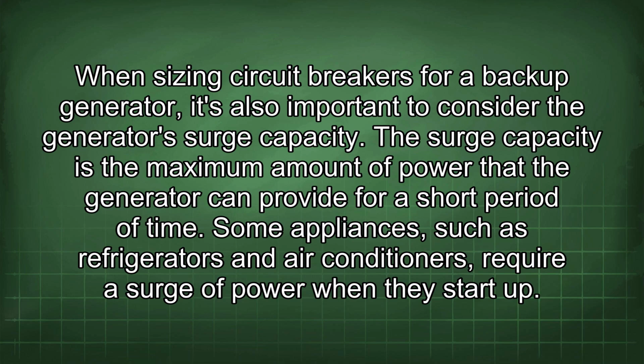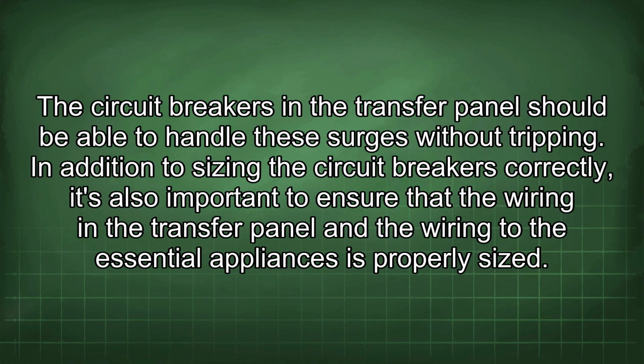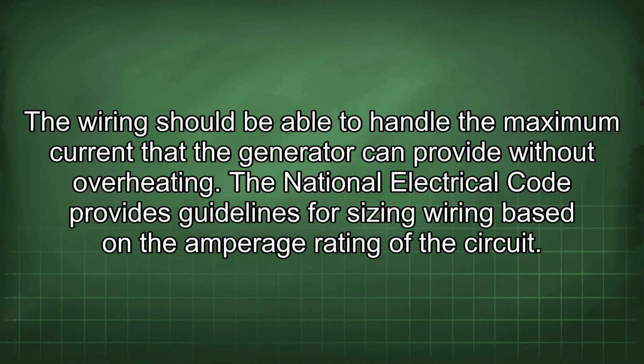Some appliances, such as refrigerators and air conditioners, require a surge of power when they start up. The circuit breakers in the transfer panel should be able to handle these surges without tripping. In addition to sizing the circuit breakers correctly, it's also important to ensure that the wiring in the transfer panel and the wiring to the essential appliances is properly sized.